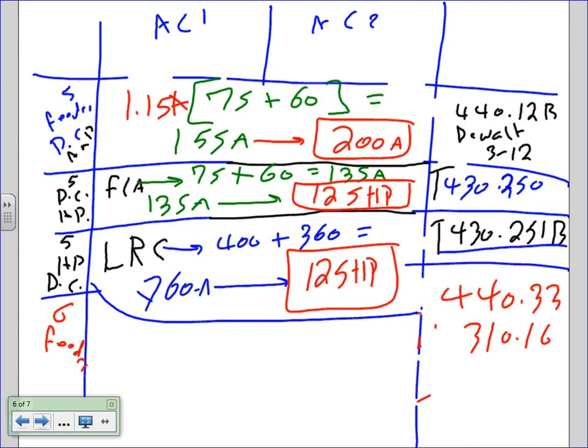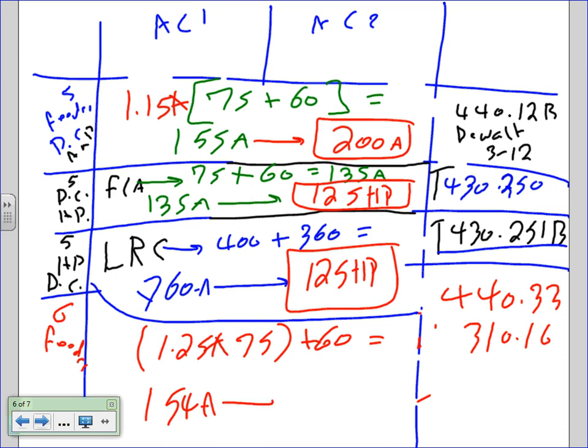The last thing in this system, guys, before I switch is 1.25. The feeder conductor, piece of cake, 1.25. Multiply this by 75, the largest, fattest, fluffiest motor, plus the full load amp of the others. That will translate into 154 amp. Take this one to 3.